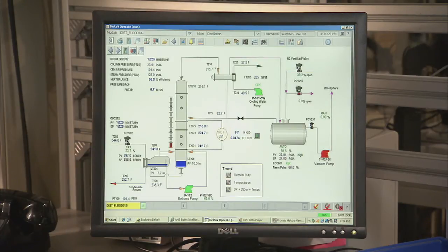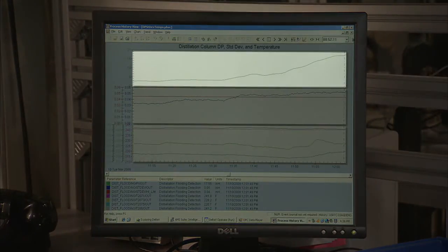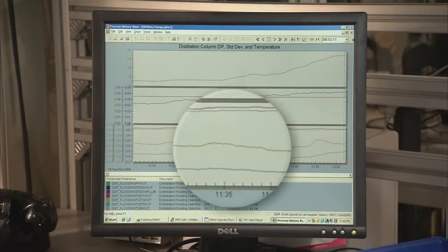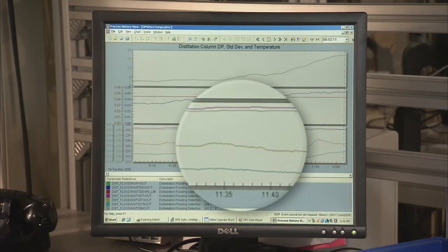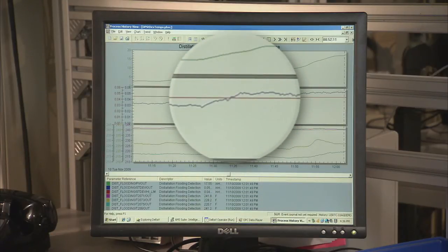Clicking on the alarm banner will allow you to investigate further and give you access to the process diagnostic trends. As you can see, in addition to just measuring the pressure, the 3051S also measures the process variability inside the column. Now, at the onset of flooding, the temperatures along the column may not have changed, but here we see a large change in the pressure standard deviation.